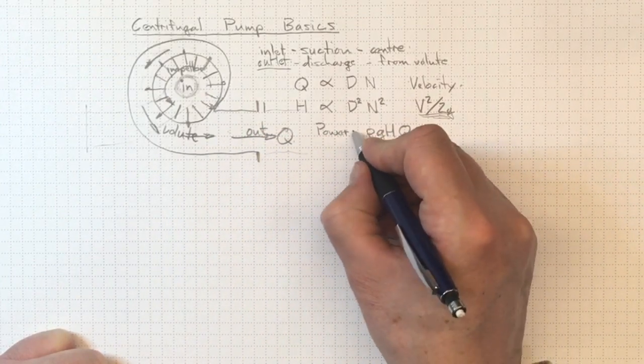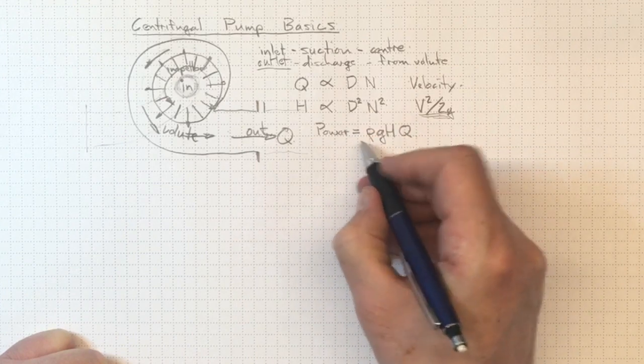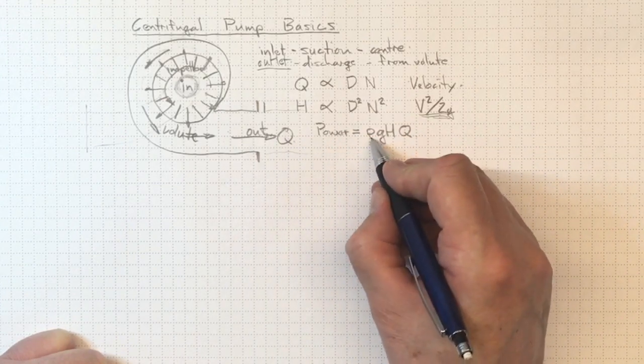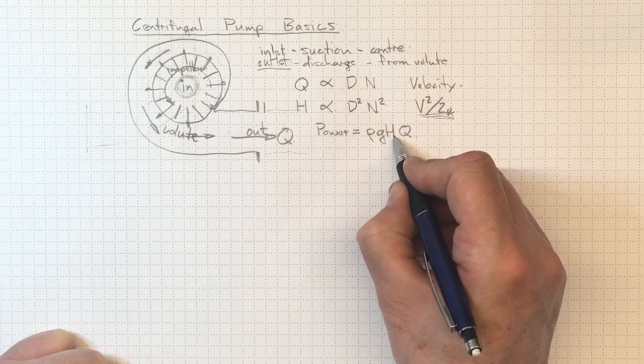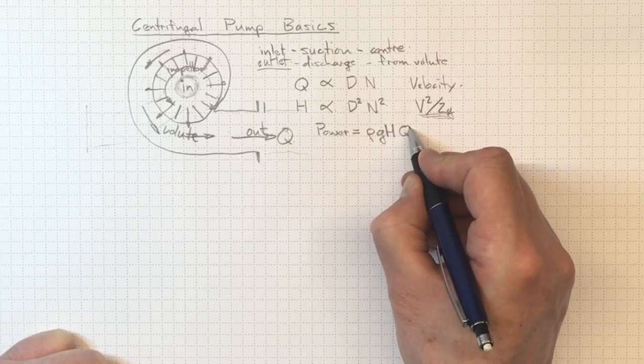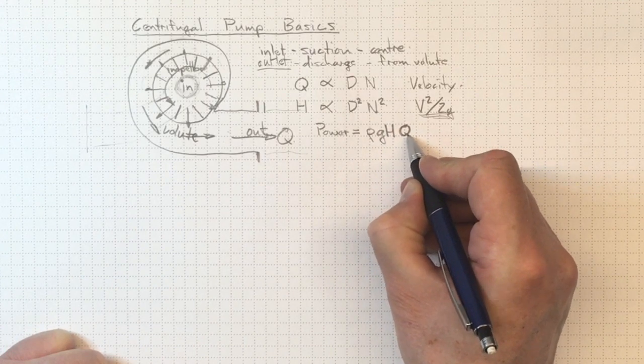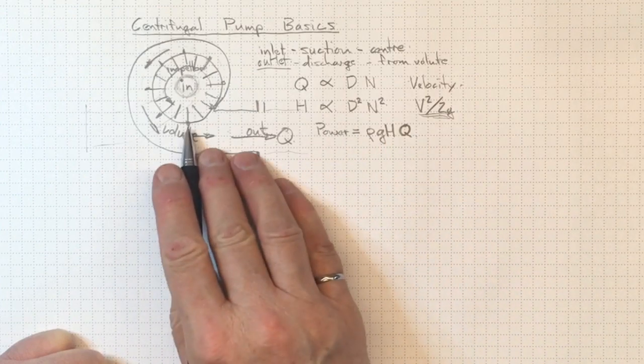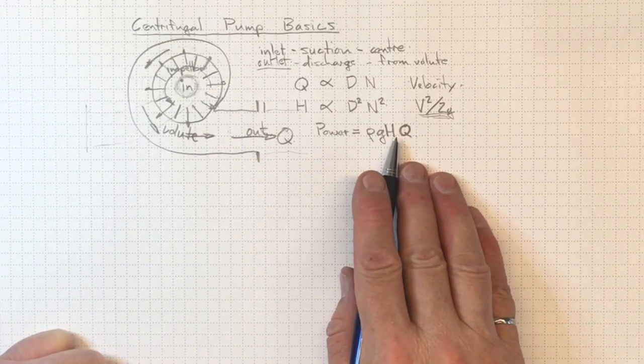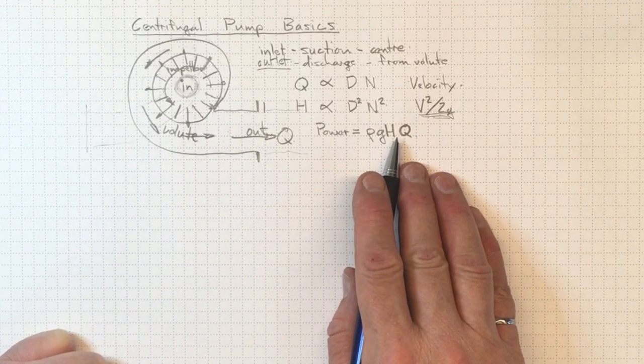So we see a PV work term, and the power taken to drive the fluid out of the pump depends on density, gravity, the head rise across the pump, and the flow rate through the pump. So those are the conditions that we'll see with just about any centrifugal pump.